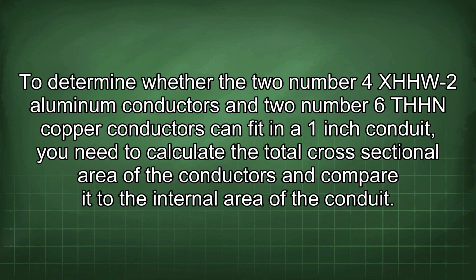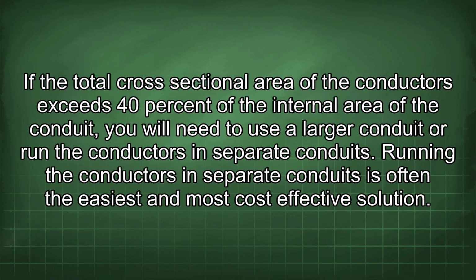To determine whether the two number 4 XHHW-2 aluminum conductors and two number 6 THHN copper conductors can fit in a 1-inch conduit, you need to calculate the total cross-sectional area of the conductors and compare it to the internal area of the conduit. If the total cross-sectional area of the conductors exceeds 40% of the internal area of the conduit, you will need to use a larger conduit or run the conductors in separate conduits. Running the conductors in separate conduits is often the easiest and most cost-effective solution.